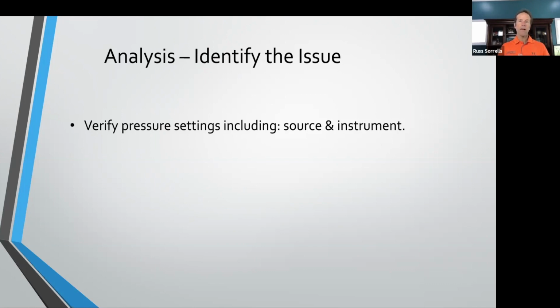Now, we recommend that you put the self-test cap on the bottom of the instrument before you try to adjust the test pressure. And again, when you adjust the test pressure, the easiest way, in some cases, to do it is just to press start and then press hold, and then you can adjust the regulator up and down. Now, that's assuming that your instrument min-max settings are in a window that allows you to make those adjustments.